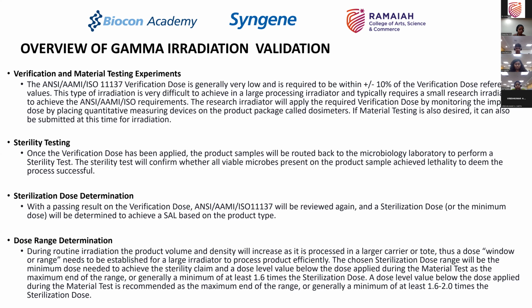But what is important to remember is that we need to fix a window, because in no irradiator at a commercial scale will you exactly see the precise dose of 15 or 20 all the time. There will be a variation, because remember the construction of it, remember the storage rack, the rack that we spoke about in the earlier presentation. So based on this, you have to fix a window and work with a window.